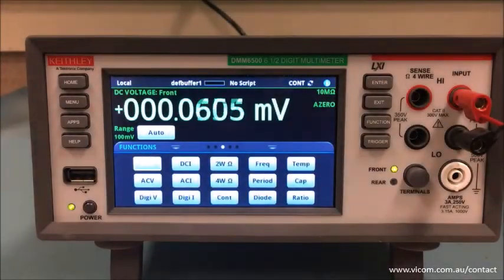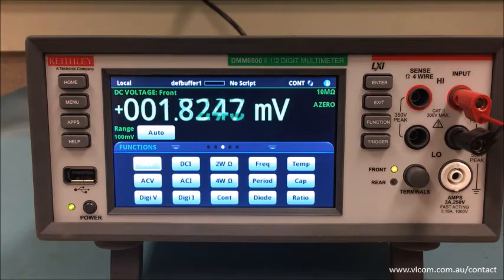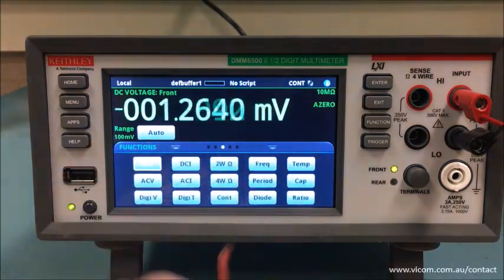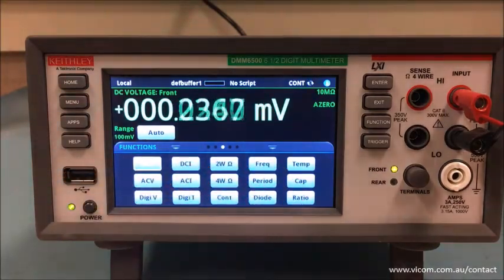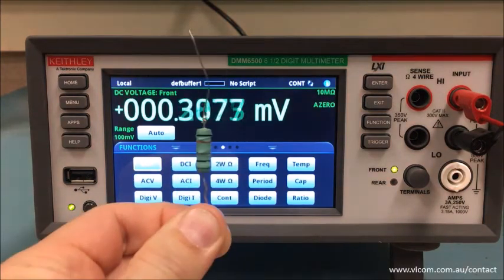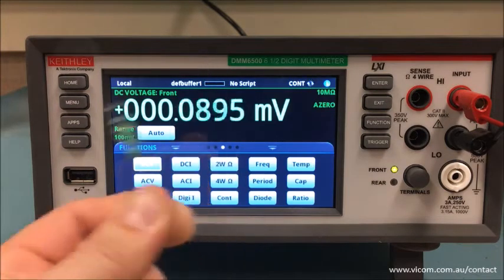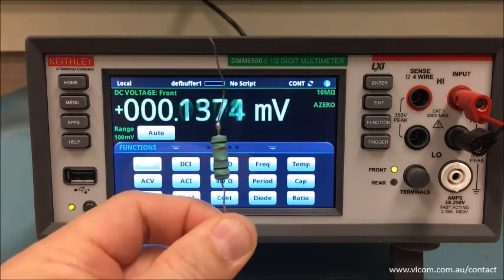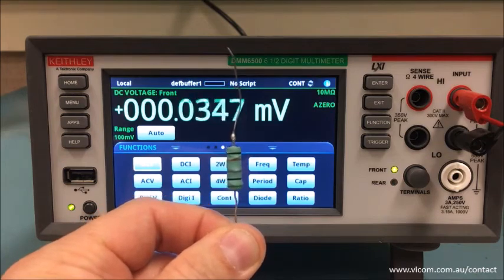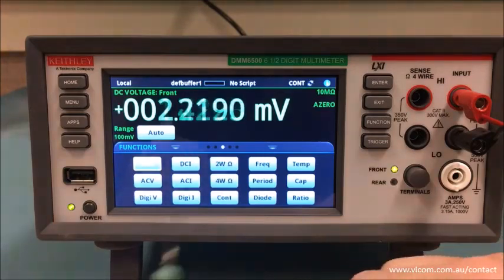Let's start by making a common two-wire resistance measurement. As you can see on the right-hand side here, I have my high and low terminals connected to my test leads. I have a selected device under test which is 50 milliohms with a 1% tolerance, meaning my low and high values are 49.5 milliohms and 50.5 milliohms. Therefore, the resistance value I measure by my meter should be somewhere in between those.